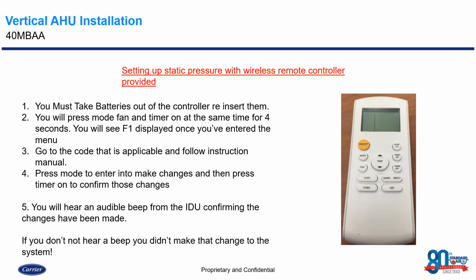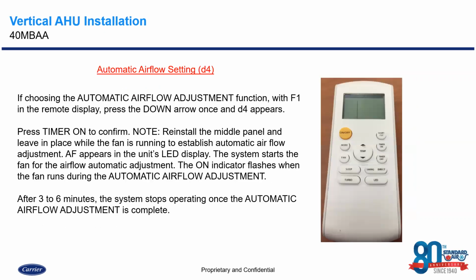You're then going to press and hold the mode, fan, and timer on button simultaneously until you see an F1 display on this screen. Now once you see that F1 come up on the screen, you then want to use your temperature up and down buttons to navigate to either one of these two codes. The first one is going to be D4.